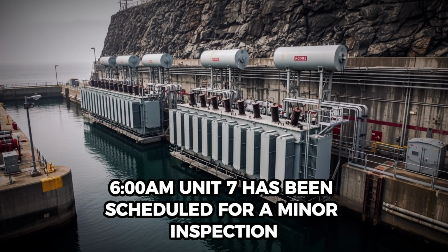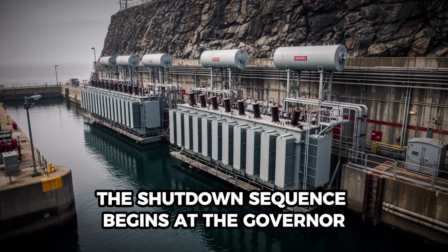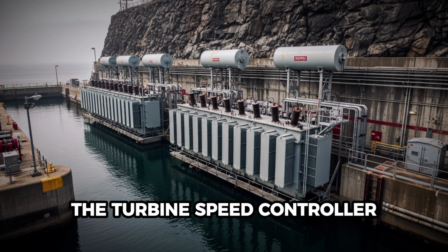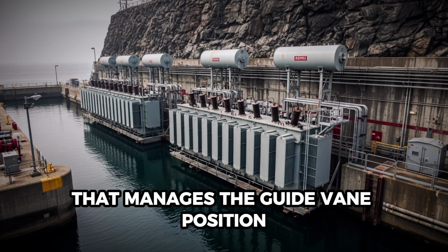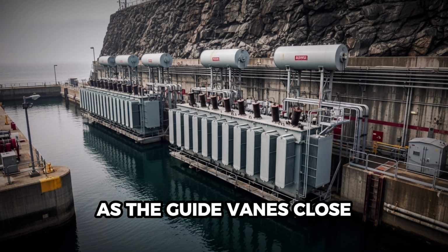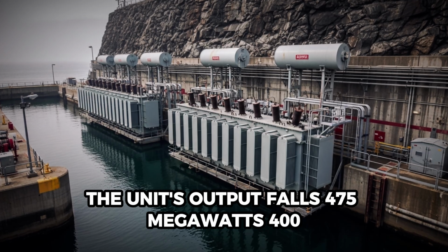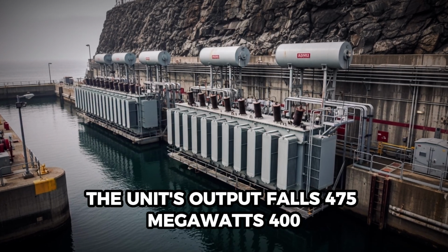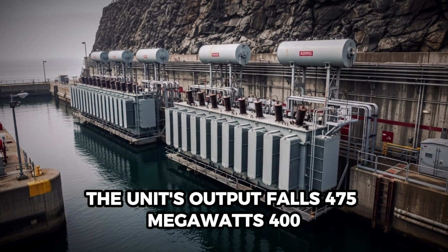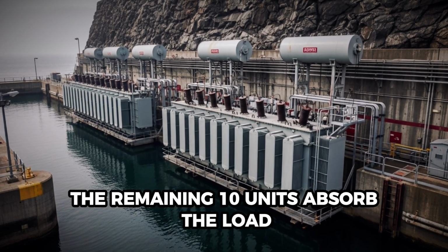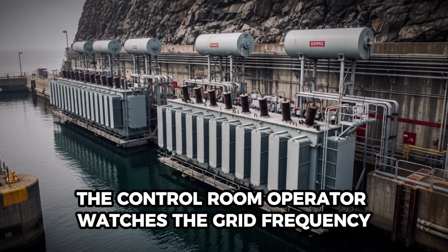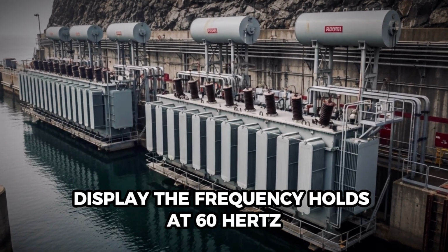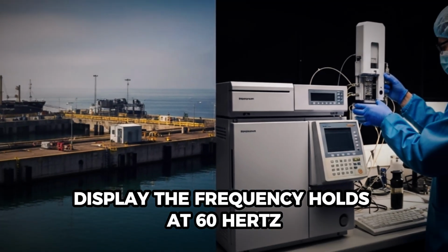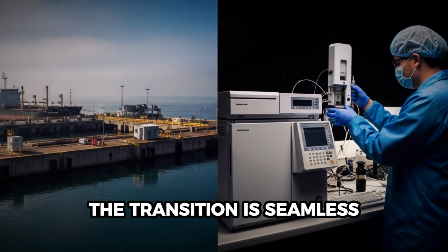6:00 a.m., Unit 7 has been scheduled for a minor inspection. The outage window is 14 hours. The shutdown sequence begins at the governor, the turbine speed controller that manages the guide vane position. As the guide vanes close, the flow through the turbine reduces. The unit's output falls. 475 megawatts, 400, 300, 200. The remaining 10 units absorb the load. The control room operator watches the grid frequency display. The frequency holds at 60 Hz. The transition is seamless. At zero output, the unit disconnects from the grid.